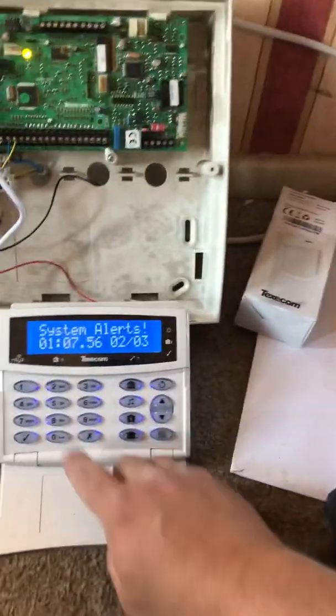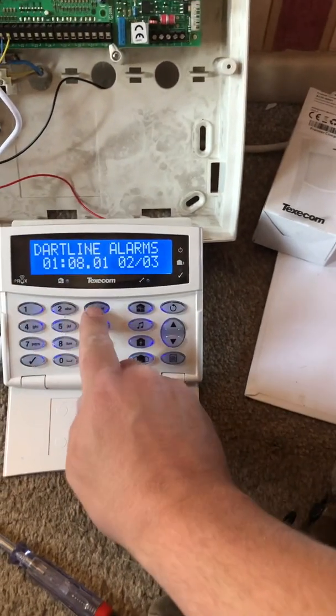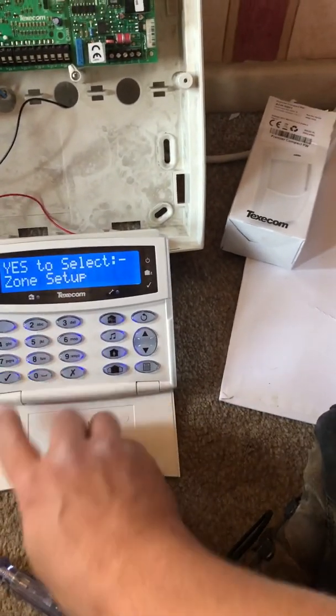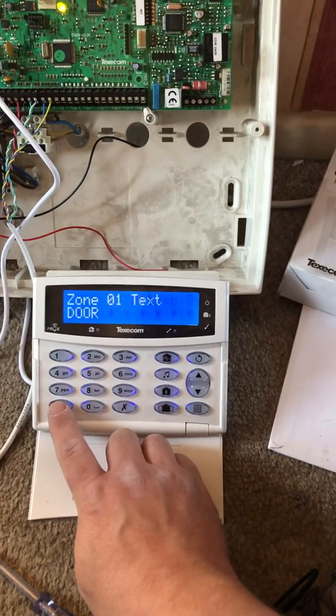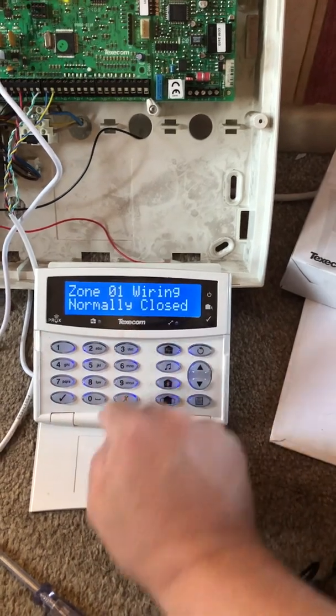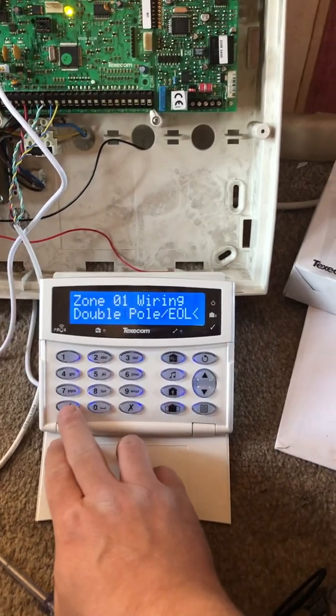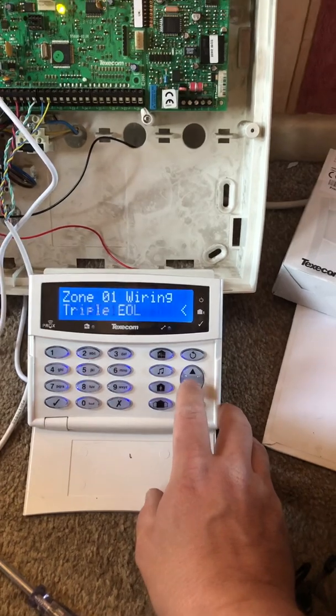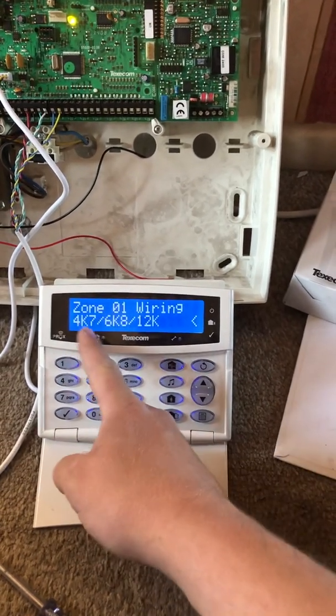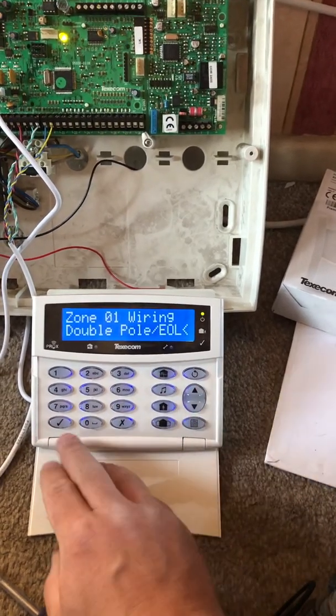Before we do anything else, we need to adjust the system to accept the change. Pin in the engineer code, go to zone setup, find the zone you want, and press tick until you get to 'wiring'. Press X and change that to 'double pole end of line'. On some systems you might have to physically go down and find the resistance settings, but on this one it's just double pole end of line.